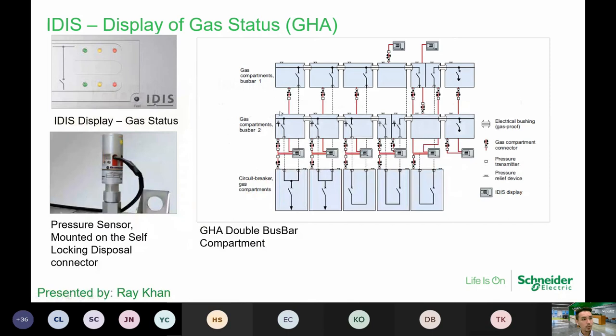So for the GHA model, which is the double gas tank, it comes with a display, which is called the IDIS, which is the gas status. All right, so the green indicates that it's working fine. The yellow is a pre-warning alarm. And then after that, there's red. Once it goes into red, there'll be a main warning. So it comes with a pressure sensor mounted on the self-locking disposal connector. All right.